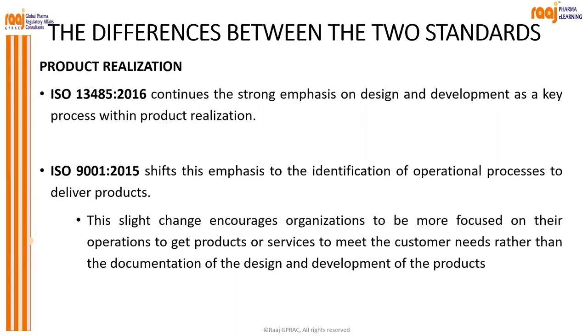And in the case of medical devices class 1, like us, we are going for class 1 or class 2 products, wherein the risk is very less, minimal, and that is why we have excluded the design and development clause from our quality manual. We are able to justify this because we are just adapting the customer-specific design and requirement; as per the customer-specific requirement we are going to manufacture our product, and that is why the design and development clause is not applicable in our case.